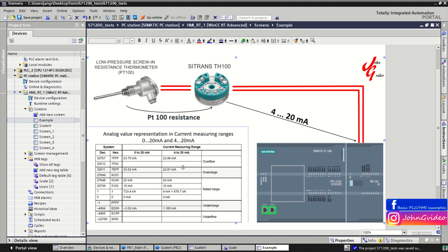When we have overrange, this corresponds to a specific range of numbers in our PLC program, and when there is overflow, this is another range. We receive this range from the analog input card, saved in the tag which is linked to the analog input of your analog input card. There is also underrange and underflow, each corresponding to their own range of numbers.